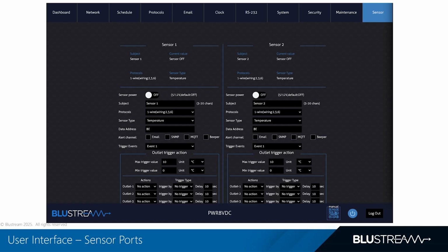Each sensor gets its own setup, a label, the protocol or type, and data address. You then define minimum and maximum thresholds and optional delays to avoid nuisance trips. When a threshold is crossed, the PDU executes per-outlet actions that you choose.